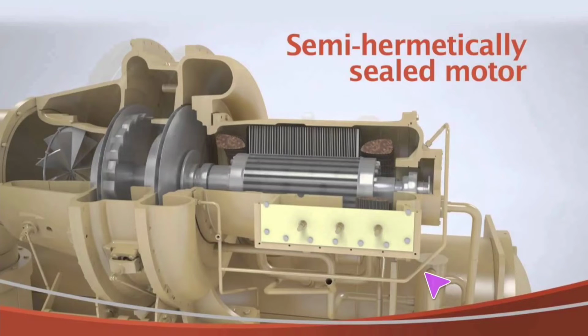It's got several jobs it functions in. It's more critical to what we're discussing now, and the fact that this is what prevents a lot of oil from getting back into the condenser, and specifically the evaporator. It also allows the oil tank or the oil reservoir to vent its vapor that may collect into the top of the tank back out into the evaporator.